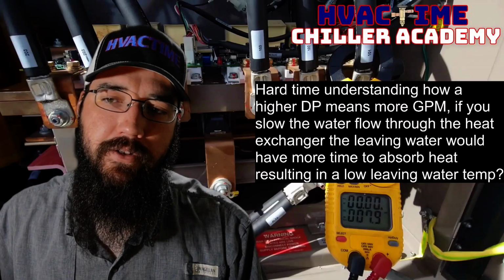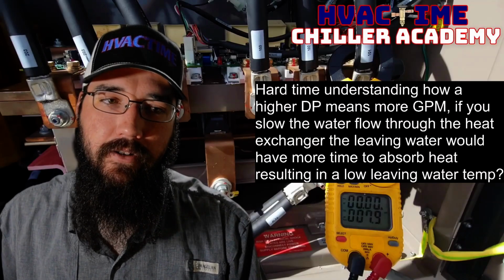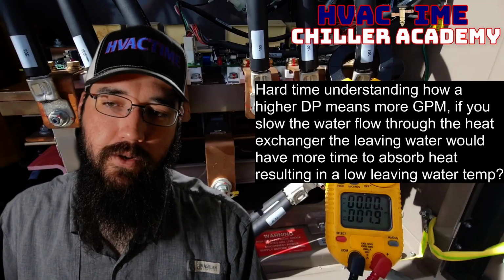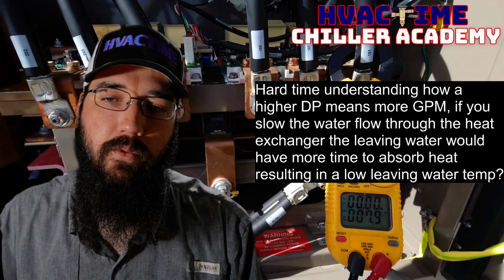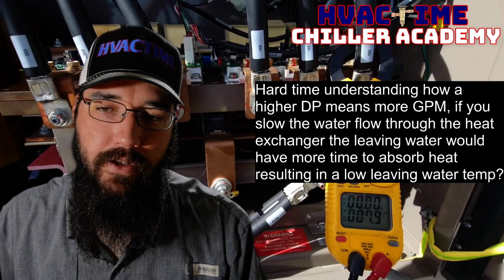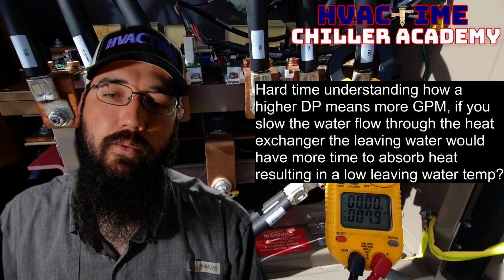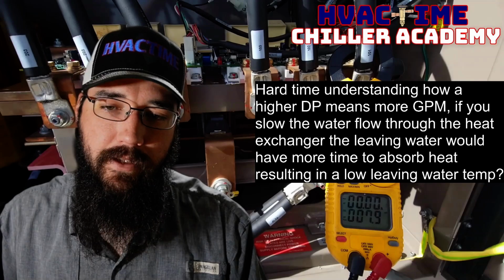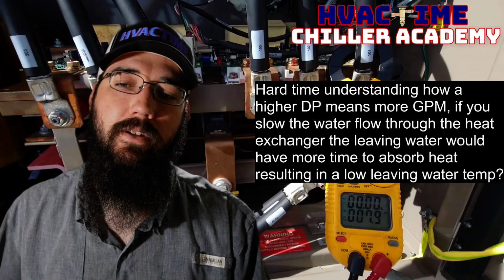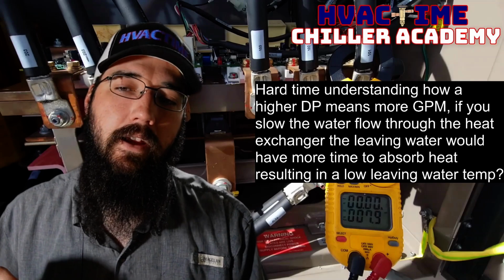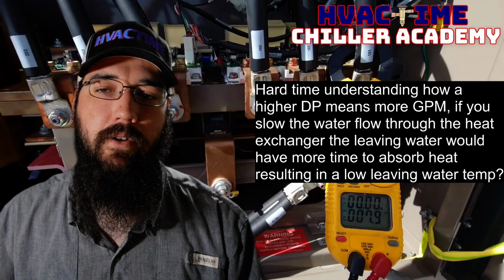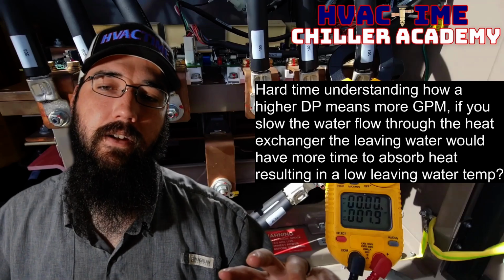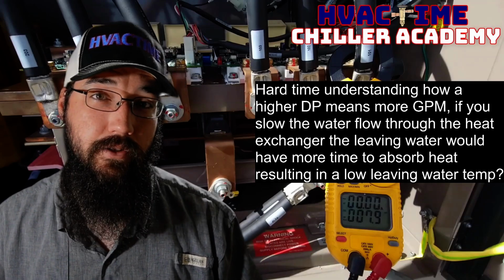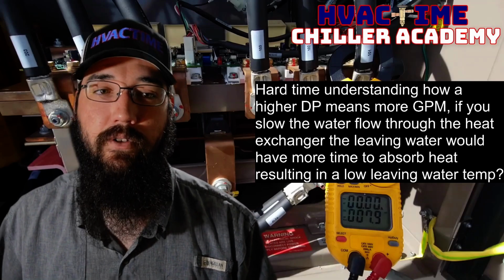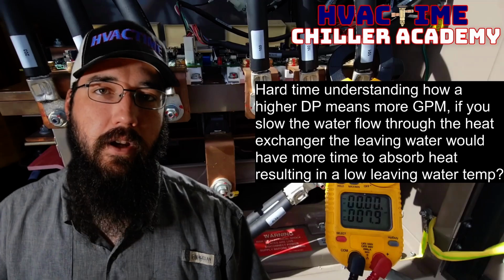Hard time understanding how a higher DP means more GPM. If you slow the water flow through the heat exchanger, the leaving water would have more time to absorb heat, resulting in a lower leaving water temperature. So we do have to be careful that we're not confusing DP for differential pressure and TD for differential temperature. Be cautious of that.